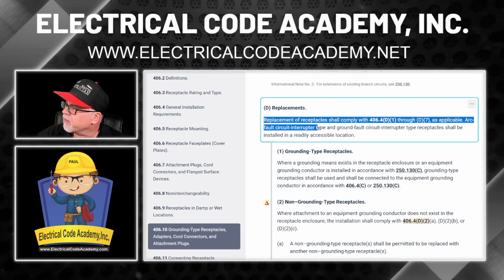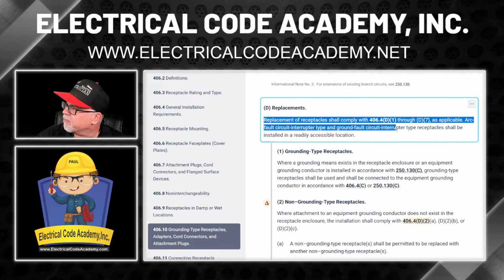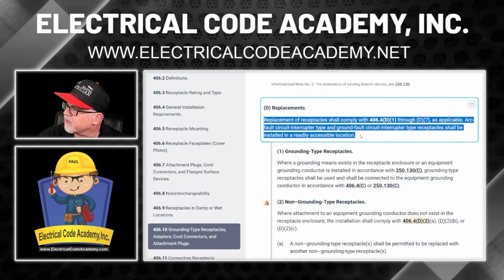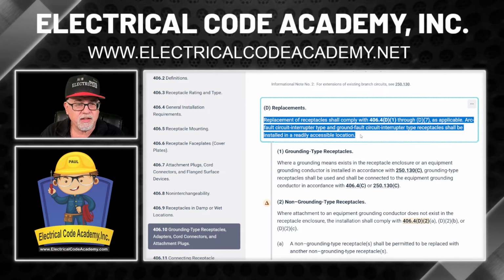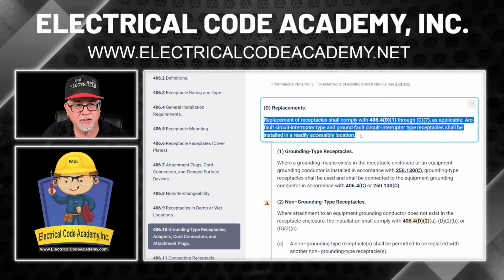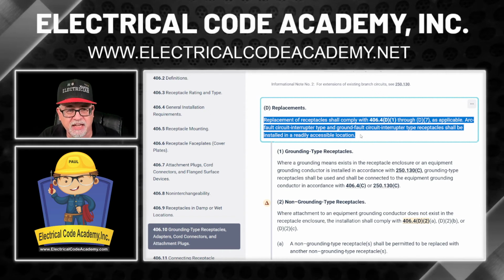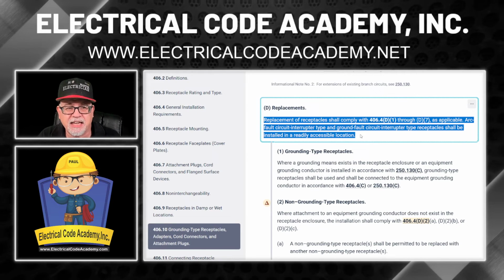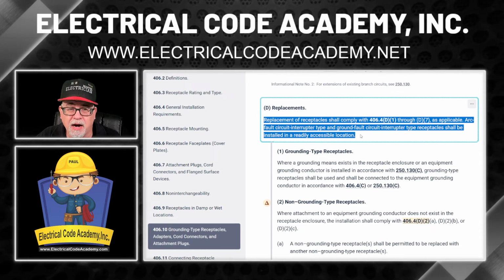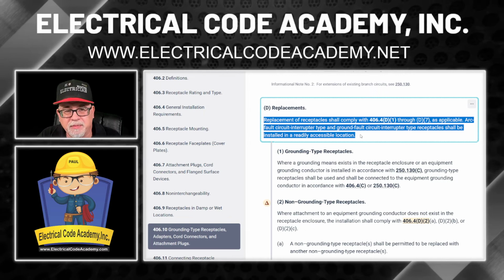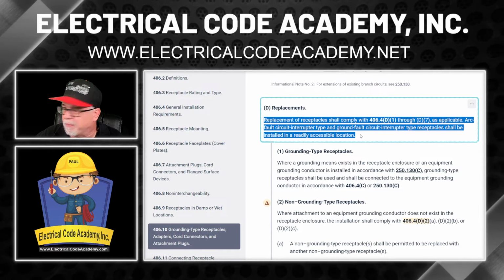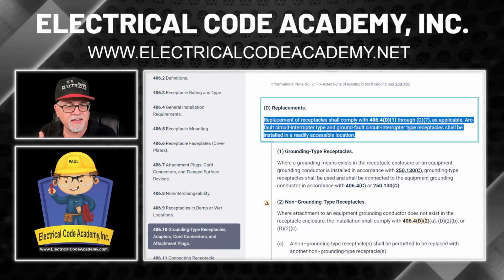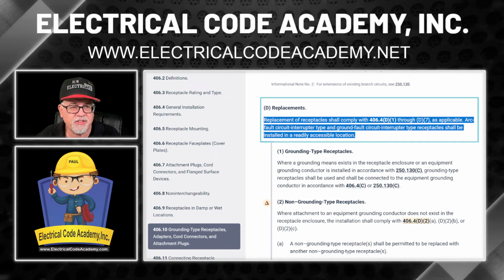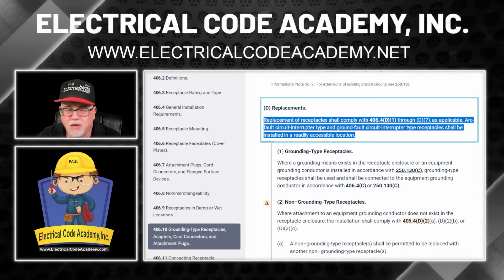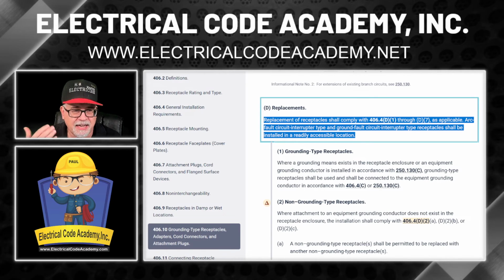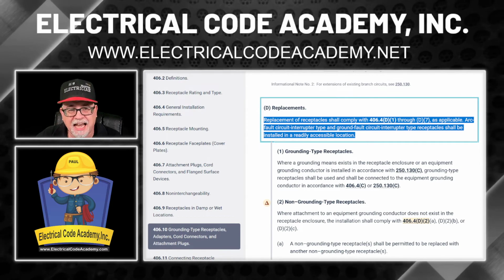Arc fault circuit interrupter type and ground fault circuit interrupter type receptacles shall be installed in a readily accessible location. So one of the options is if he was replacing this receptacle in a location that back then did not require AFCI or did not require GFCI, if the location now requires it, then you're going to have to do something different. It's just not as easy as a swap, okay? We'll do that in a different video. Let's just say that this is a location where he can simply swap out that two-prong and put in his GFCI like he wants to do.